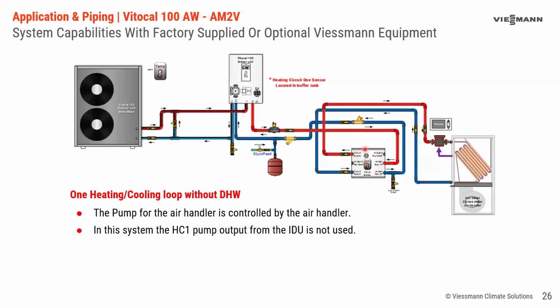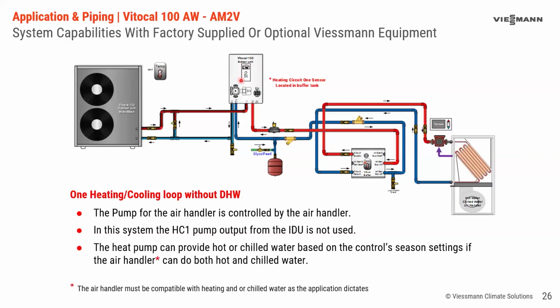Now, there is a possibility that somebody turned the thermostat to cooling and the heat pump is still in heating, which means that this pump is going to move hot water, not cold water, because the buffer tank's going to be full of hot water. So this is a seasonal changeover. You would not normally set this thermostat to automatic changeover. You would set the thermostat to be heating or cooling and switch it at the same time you switch this unit down in the indoor unit. Now, it could provide heating or chilled water depending on the control system settings. Remember, so we have this here, and the air handler would have to be suitable for that type of energy.